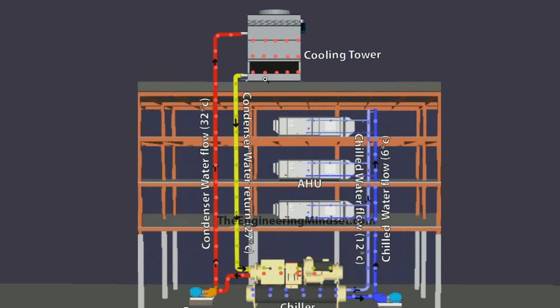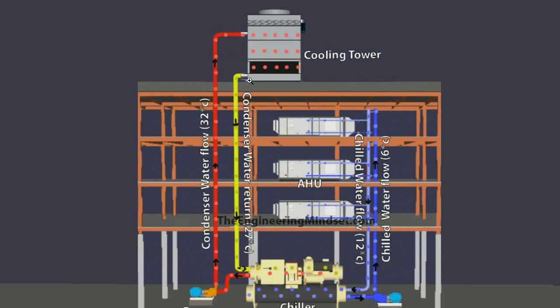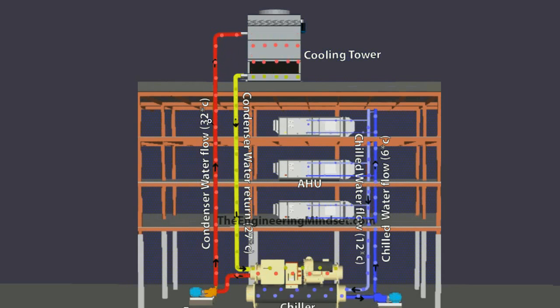Equally, if your cooling tower is unable to reject the heat being sent up to it, it's going to return at the same temperature. So if it's going up at 32 degrees Celsius and the cooling tower is unable to reject this heat — because of recirculation, water just dumping, problems with baffles — and the water is returning straight back down into the condenser, then you will not be able to reject any heat from the compressor. So it's important to monitor the temperatures of your cooling towers, the flow and return, and have good maintenance regimes on this system.